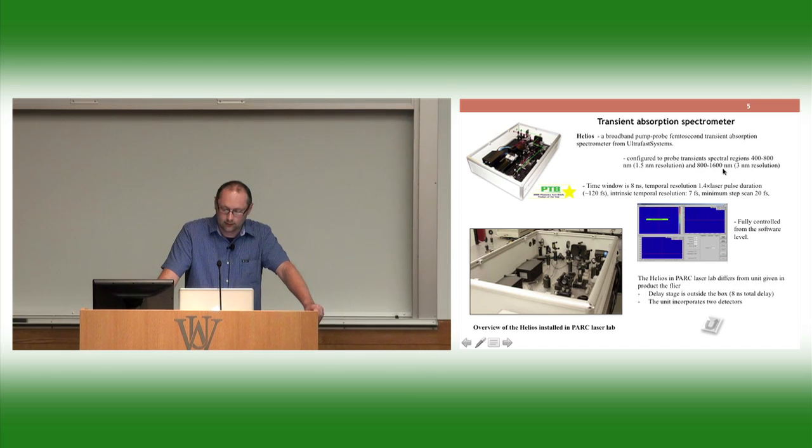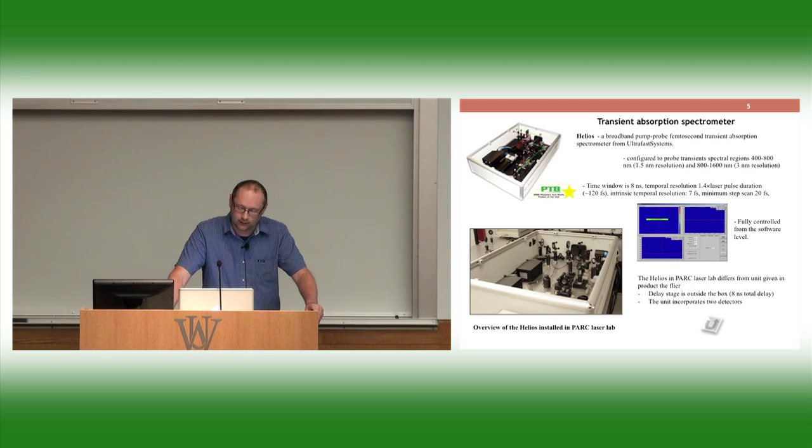It's configured to probe two spectral regions: 400 to 800 nanometers with resolution 1.5 nanometer, and the NIR range from 800 to 1600 nanometers with resolution 3 nanometers. The temporal window, what delay times we can measure between pump and probe: this unit has 8 nanoseconds delay maximum. It's really good actually. I used to work on the previous version that had only 1.6 nanoseconds. The temporal resolution of the instrument is actually defined by the company. They claim it's 1.4 multiplied by the laser duration. In our case it would be around 120-130 femtoseconds.